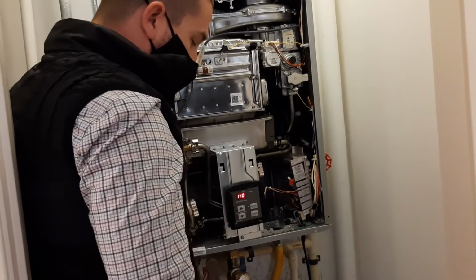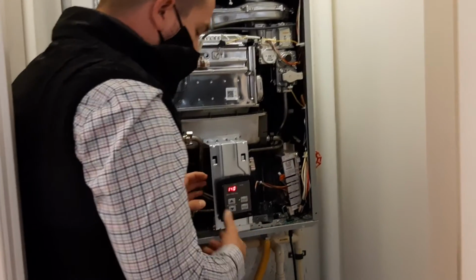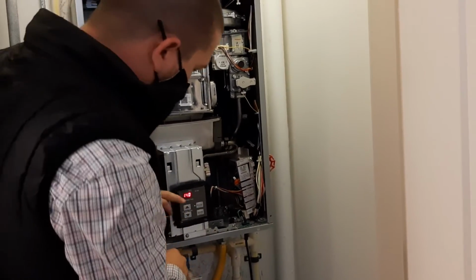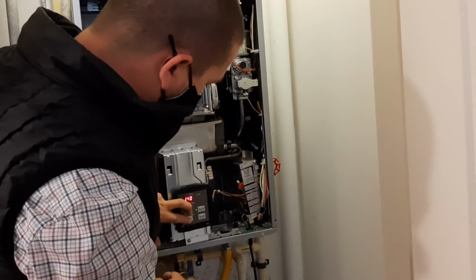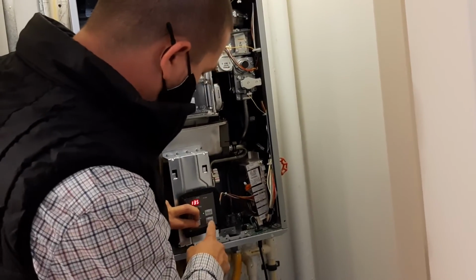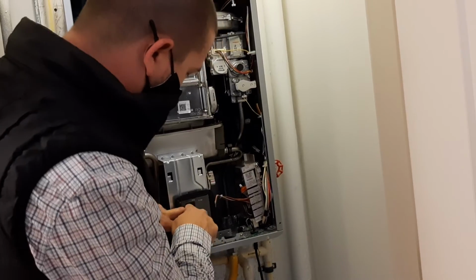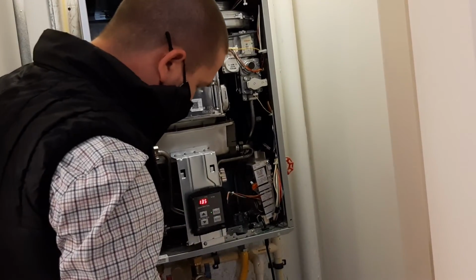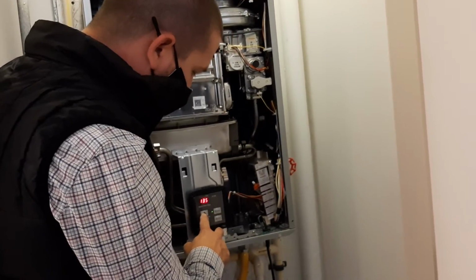Something that's probably not a bad idea to do if you're ever working on a unit, since it doesn't date and time those errors: if you hold the up arrow, the down arrow, on, off, it'll say FF. It'll flash that a couple times. And then now if we check the error history again...